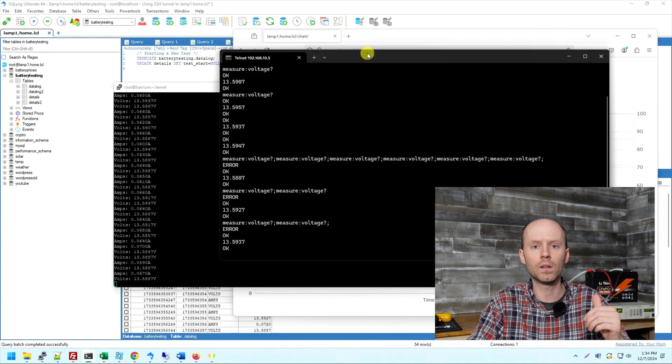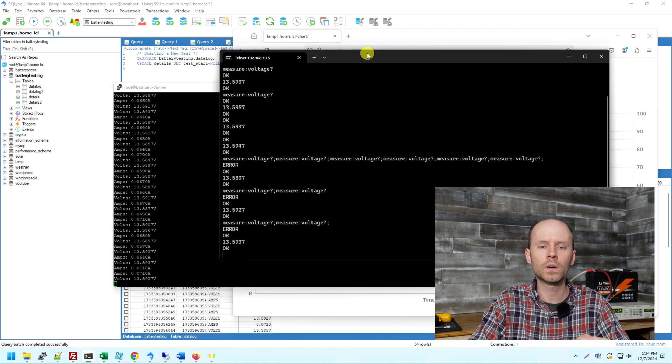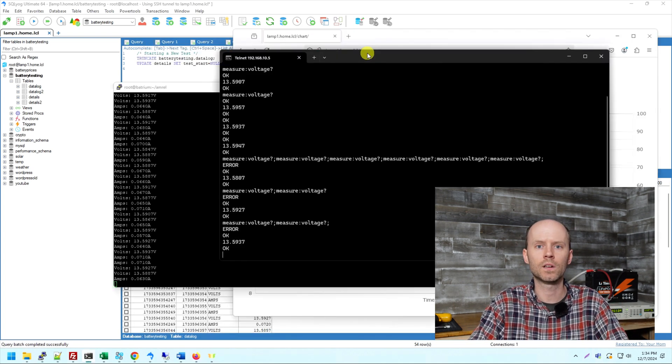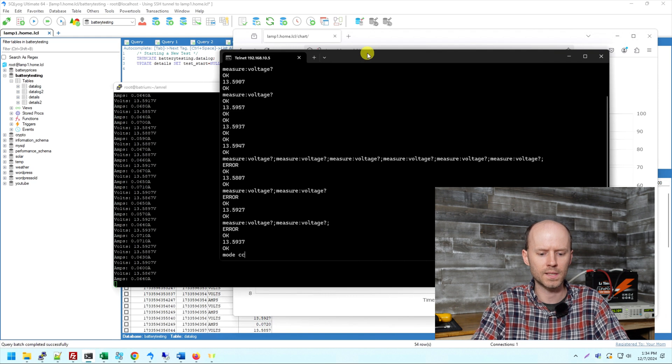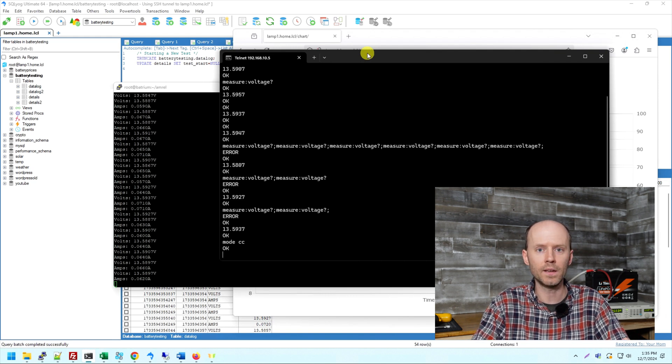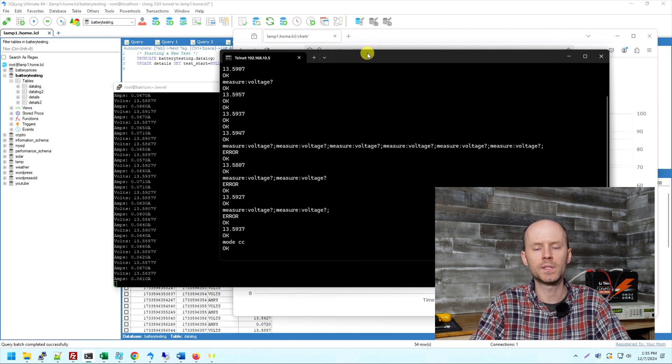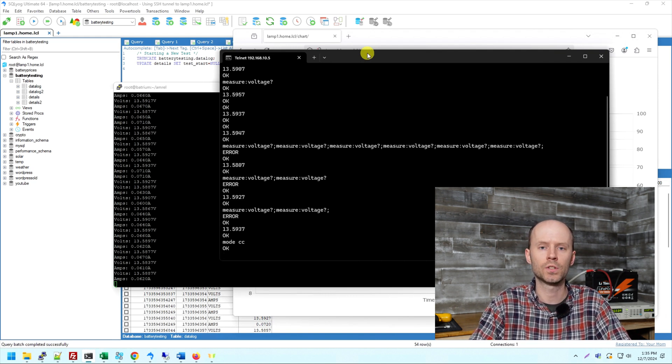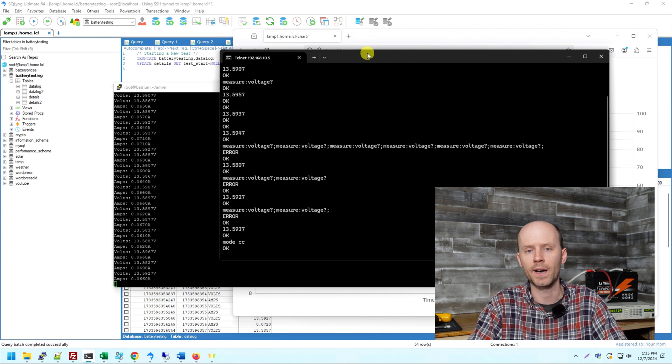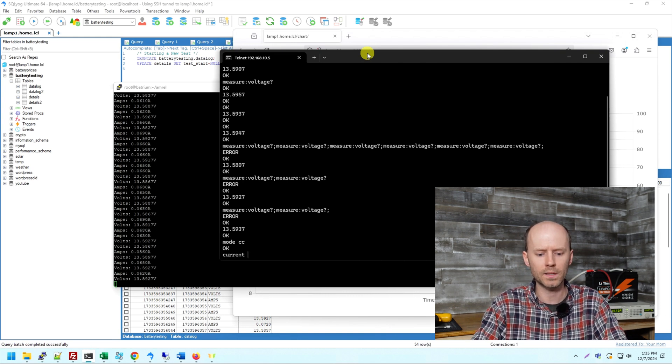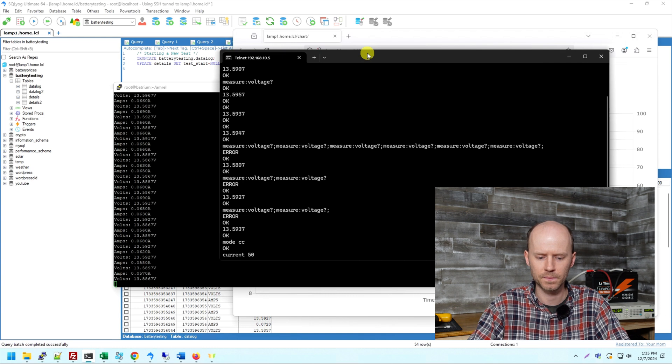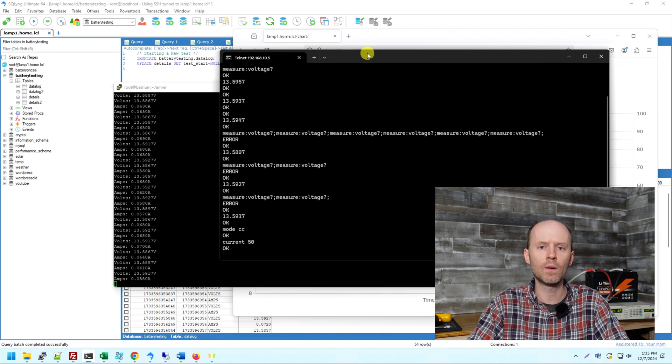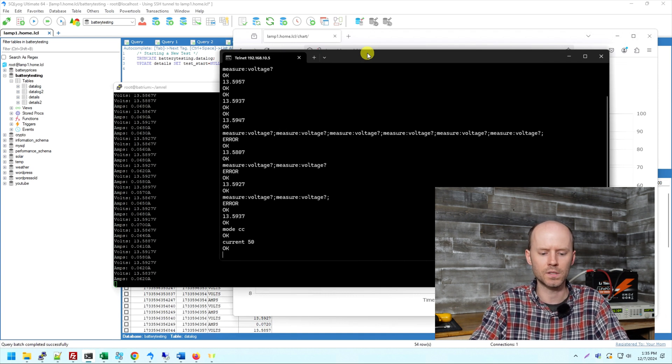So I can control that eload through the telnet prompt as well. We're going to set the constant current mode. That's done with the command mode CC. Okay. And you see it says, okay. And I'm going to do a 50 amp discharge test, which should take approximately two hours on a 100 amp hour battery. We're going to use the current command and set it for 50 amps. So now we're ready to begin the test. And that's done using the command input on.